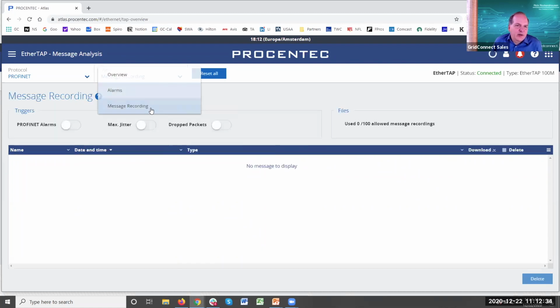And then the message recording - this is where you can set up triggers so if there was a Profinet alarm, I want to record or save the message traffic around that alarm. You can make up to 100 recordings, download them, and use those recordings in Wireshark, as I mentioned earlier in the webinar. These are the types of triggers you can set up to do that.